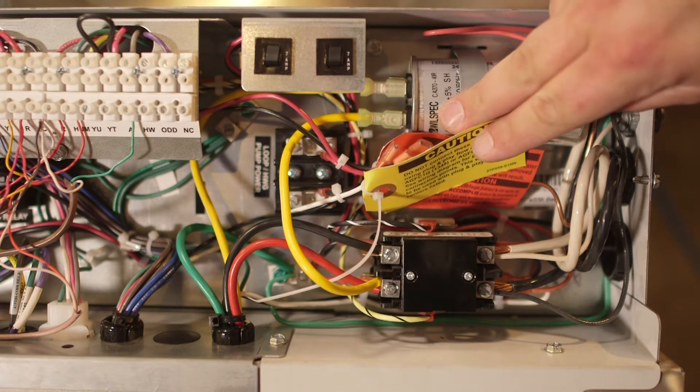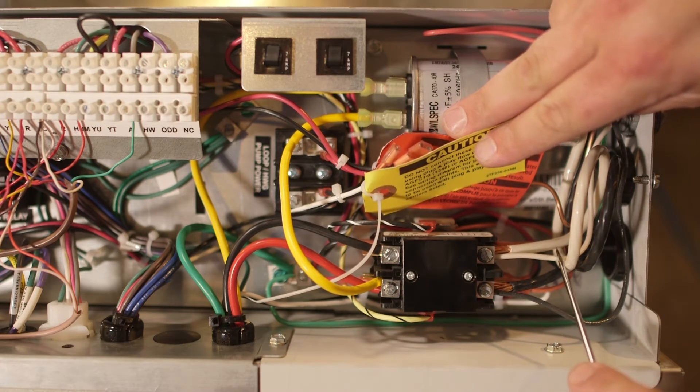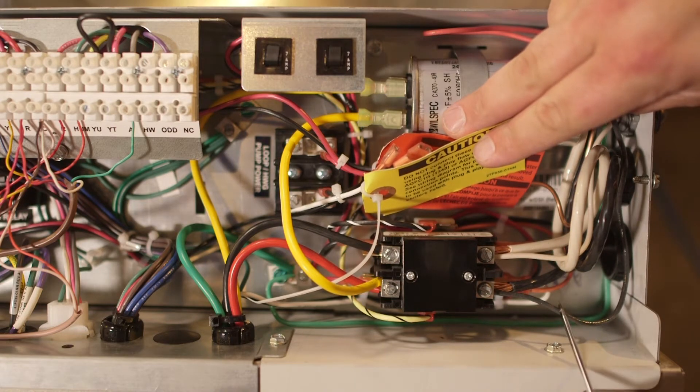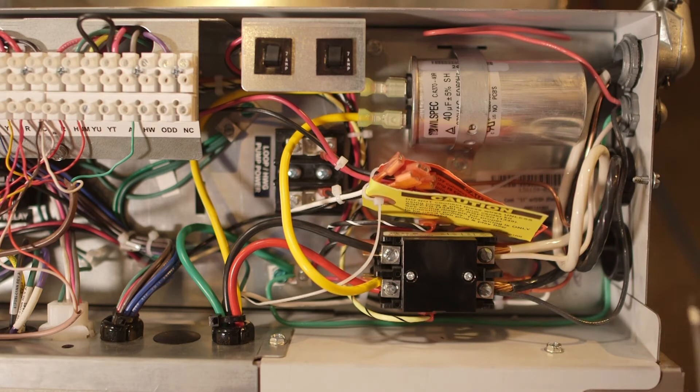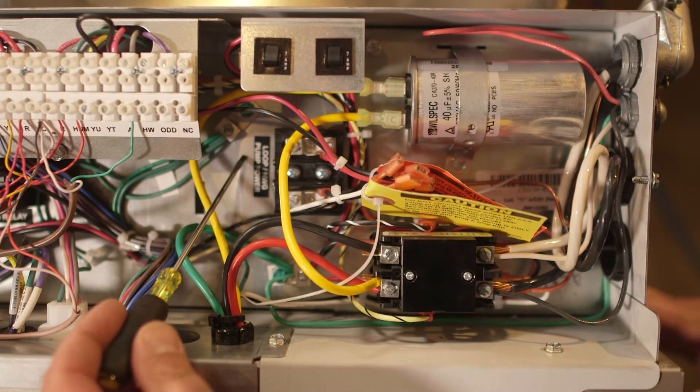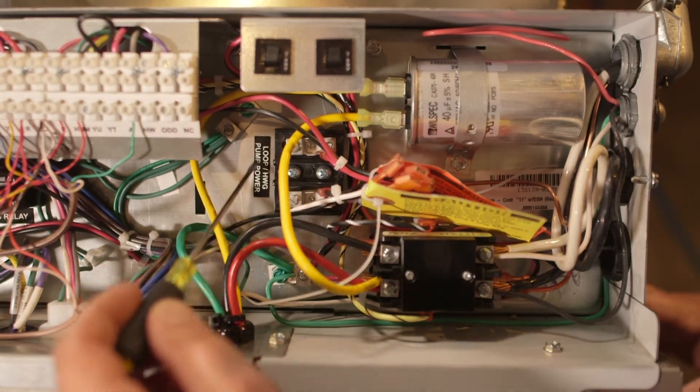Now, if you have the two pump flow center, this is really important, because the variable speed pump will still need to have the 240 volts all the time. However, the single speed pump that is also on that flow center will hook to your standard pump location. And on this particular unit, it happens to be right here.